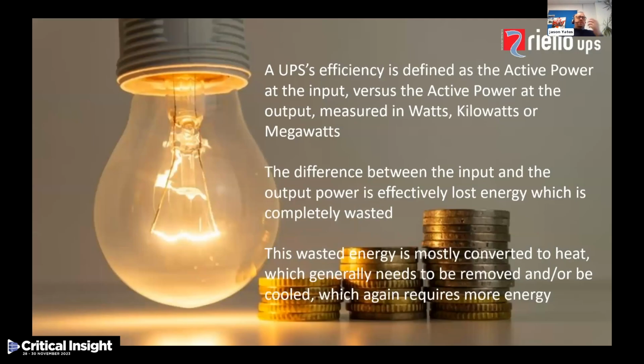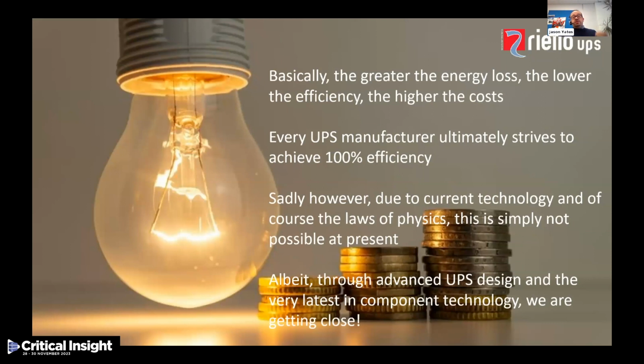A UPS's efficiency is defined as the active power at the input versus the active power at the output, which is measured in watts, kilowatts, or megawatts, depending on the size of the UPS. The difference between the input and the output power is effectively lost energy, which is completely wasted unless it can be recovered. This wasted energy is mostly converted to heat, which generally needs to be removed or cooled, which again takes more energy. Basically, the greater the energy loss, the lower the efficiency, the higher the costs. Every UPS manufacturer ultimately strives to produce a UPS that can achieve 100% efficiency. Sadly, due to current technology and the laws of physics, it's simply not possible at present, although through advanced UPS designs and the very latest in component technology, we are getting very close.